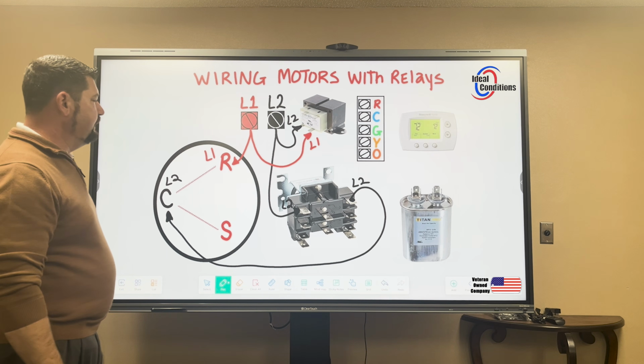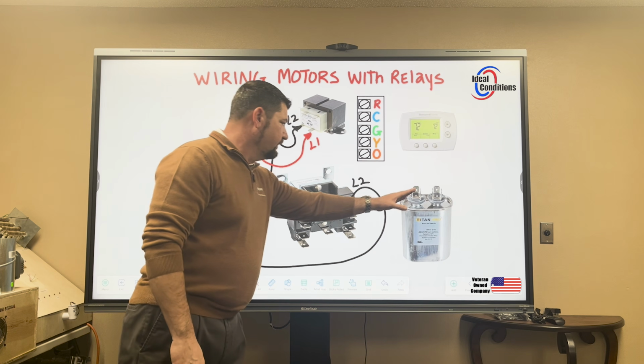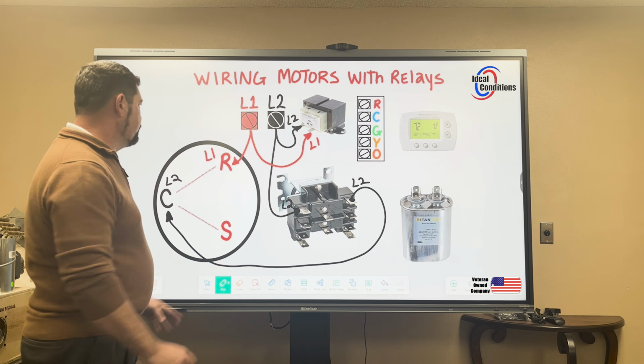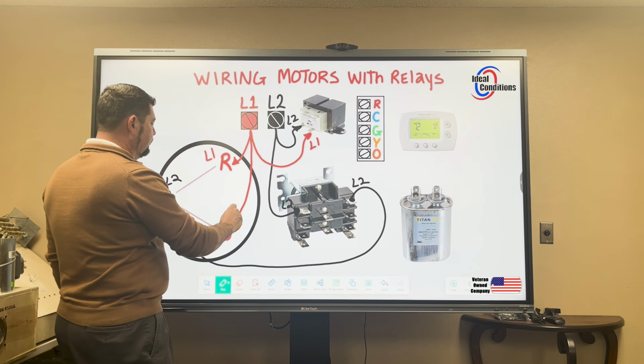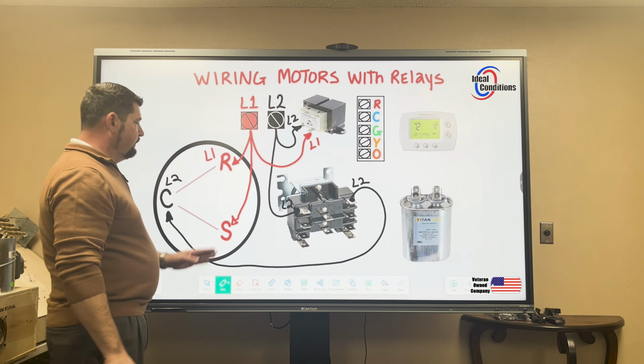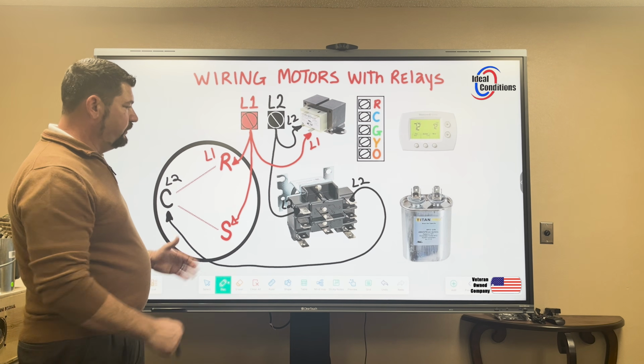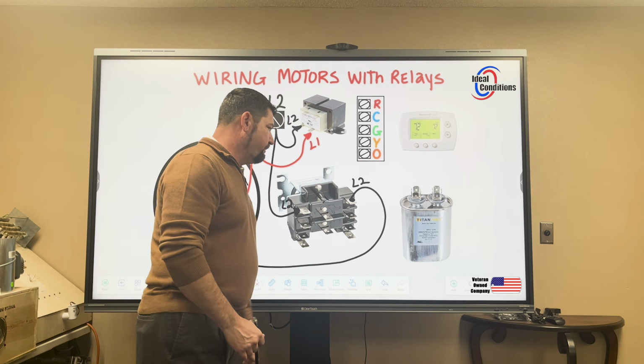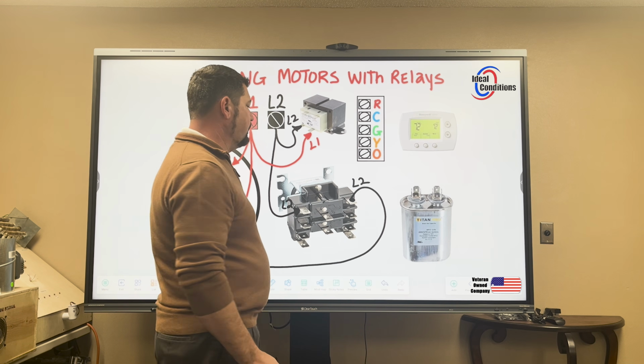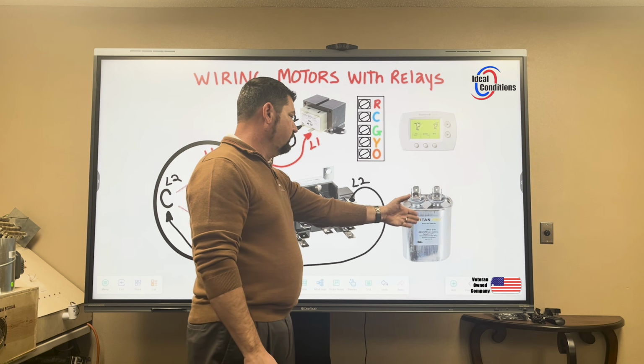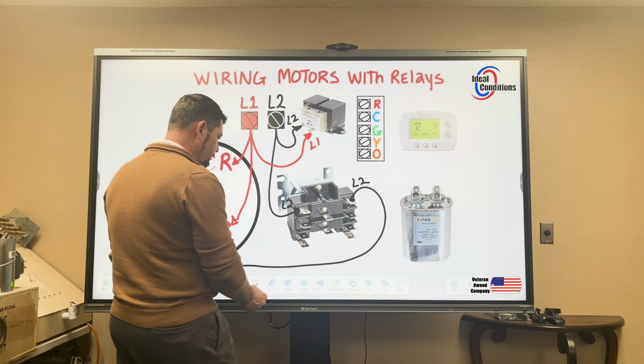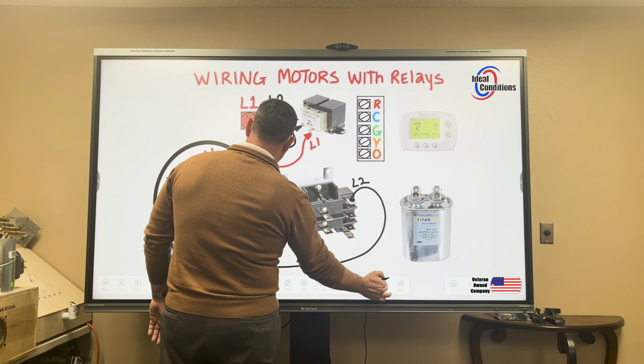Now our start winding is going to be able to get its polarity from this capacitor. So we can't just run L1 to this, because if we did that, that's not enough. We almost need to introduce what's called a third leg of power, even though it's technically not there, but we're not going to get polarity to run without a run capacitor. Let me go ahead and just delete that last step.